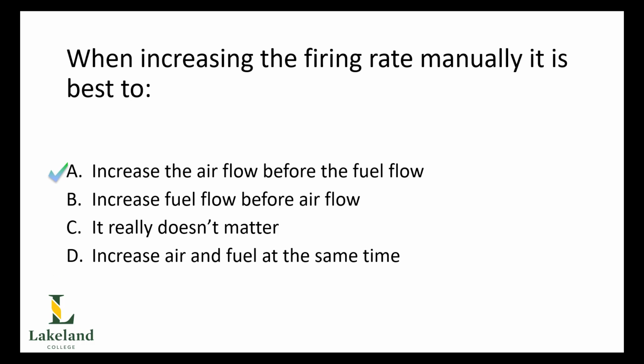Why? Because it's safer. Now I should point out that when we have our combustion controller in manual, we do not adjust the airflow and the fuel flow separately and choose which one we would do before the other. That's not what we mean by manual control. We mean we could increase the firing rate from the values that we input, but the combustion controller is naturally going to increase the airflow first before the fuel flow. So we don't separate them in terms of a control, we just mean manual. We can input the values that we require at the time we require it.